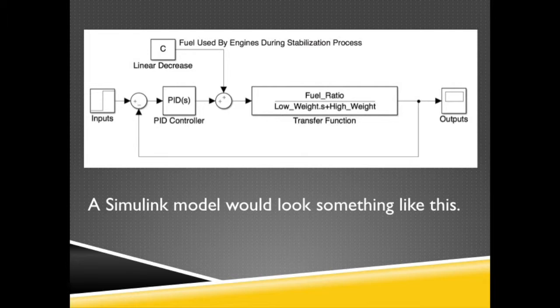First, the pilot will flip the switch to begin fuel transfer from the more full tank to the emptier one. Each tank then provides feedback to the controller throughout the fuel transfer process, telling it how much the fuel weighs. The controller will keep the fuel valve open to allow fuel to flow until the readings sent back by the tanks are equal, meaning that there is the same amount of fuel in each tank.